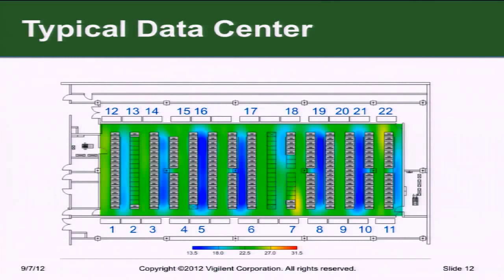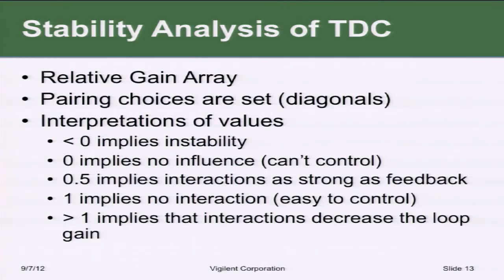This idea of pairing the return temperature with the chilled water valve or compressor - whatever the cooling mechanism is in that unit - is a pairing combination you can analyze using process control techniques commonly used when you want decentralized control but need to figure out the best way to combine a sensor with an actuator. This technique, called a relative gain array, was developed back in the 1960s by a guy named Bristol to solve just this problem: which sensor should I pair with which actuator in my process to get the best control? In this case, though, the pairing combinations are already set - we don't get a choice, since it's already dictated by the equipment manufacturer.